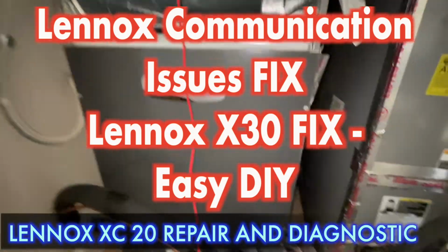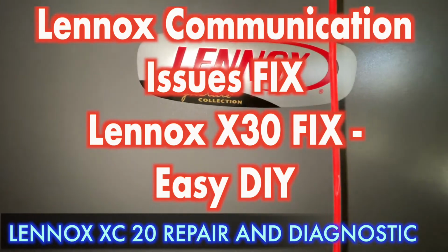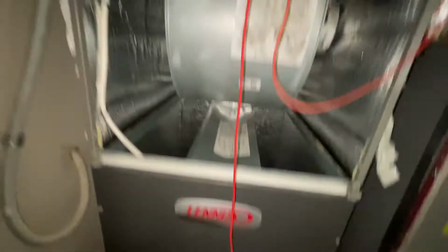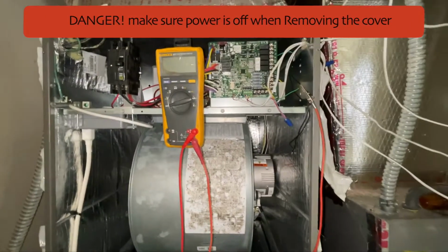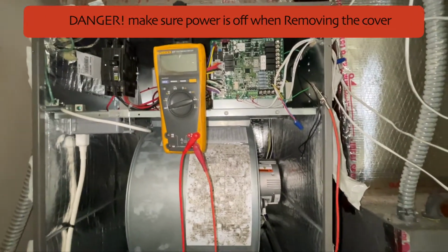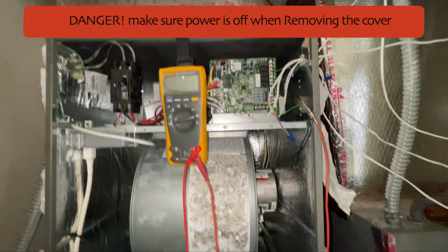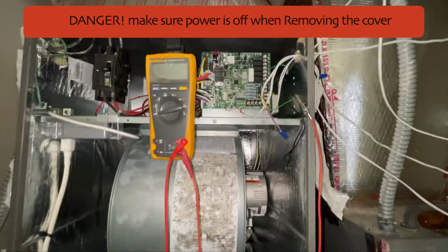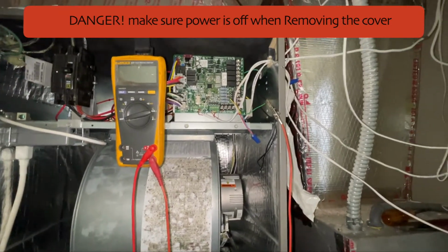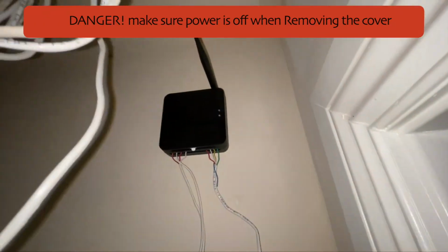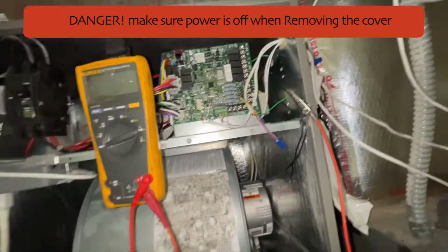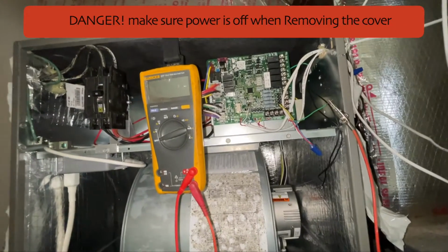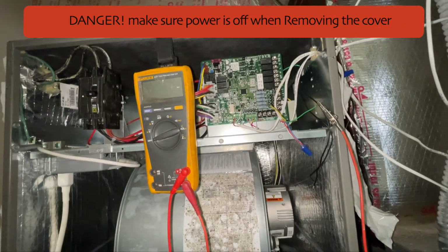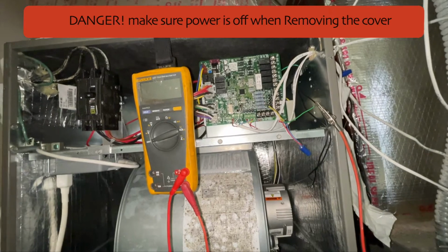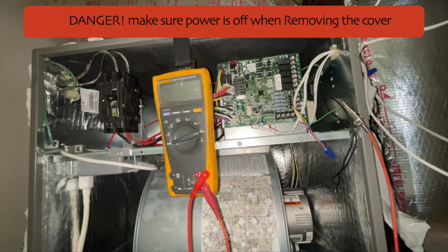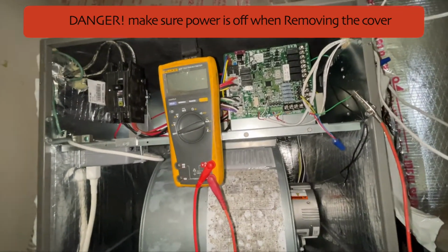Hi guys, so today I'm troubleshooting this Lennox. This is the XC20, and the problem I'm having is communication issues between the units. I was getting a communication error on my S30 thermostat, and there's the hub. For some reason it's giving a communication error. My unit was basically coming on and then it would cut off. I would restart the thermostat and the unit would come back on.